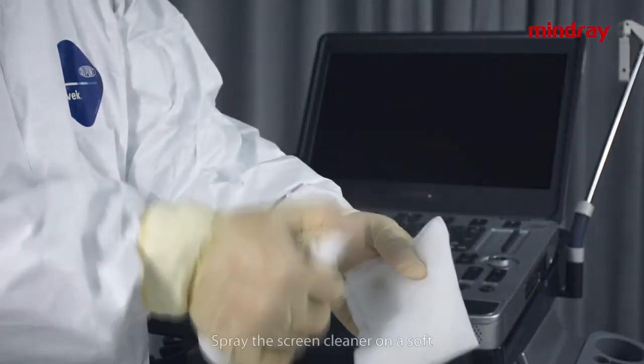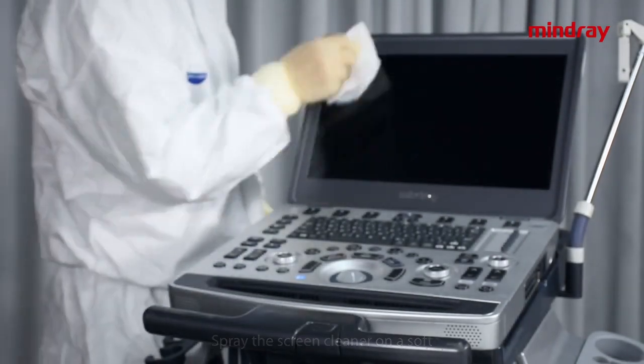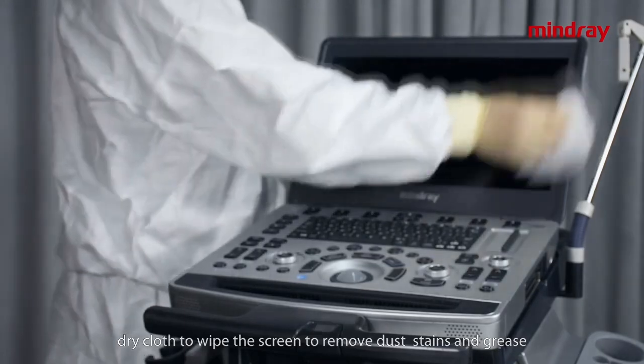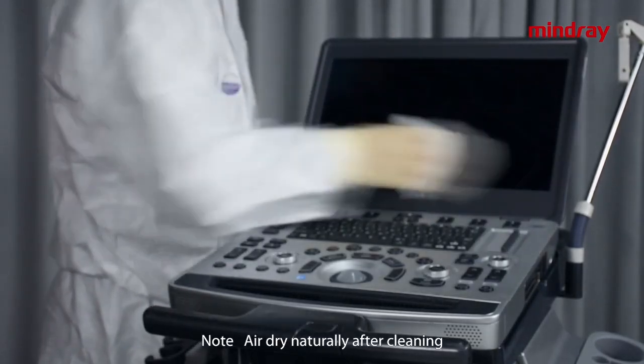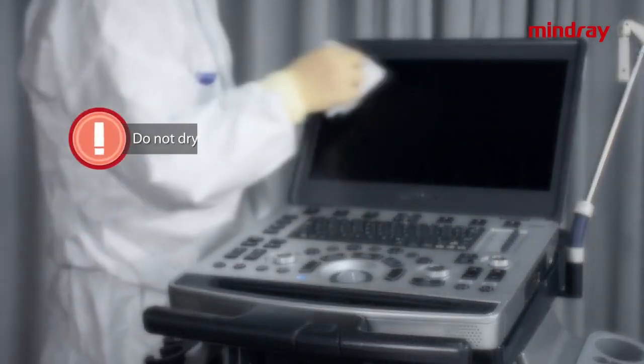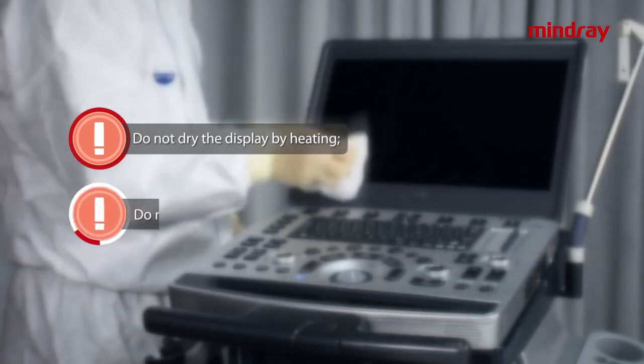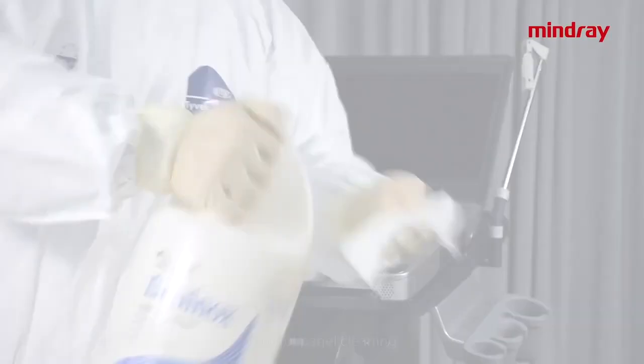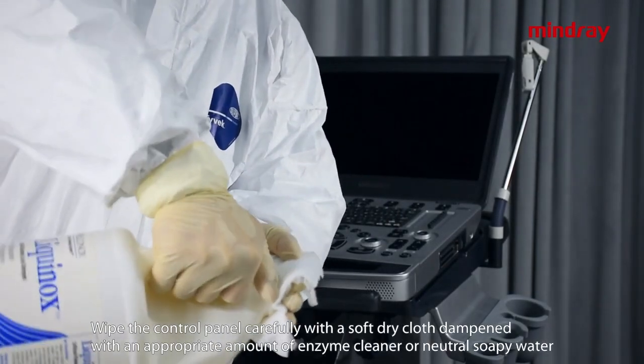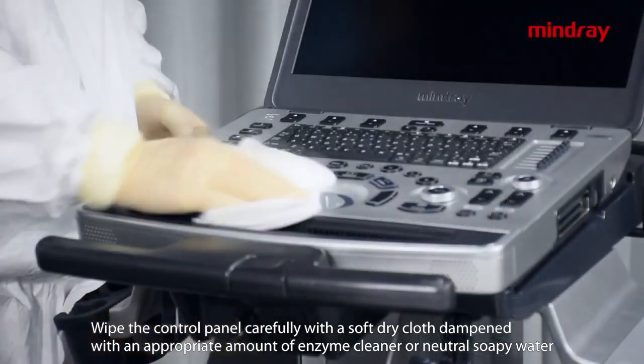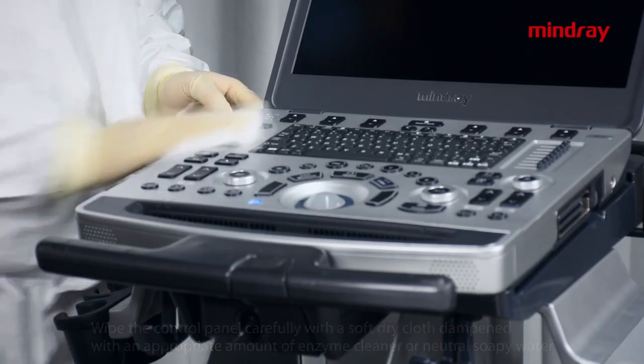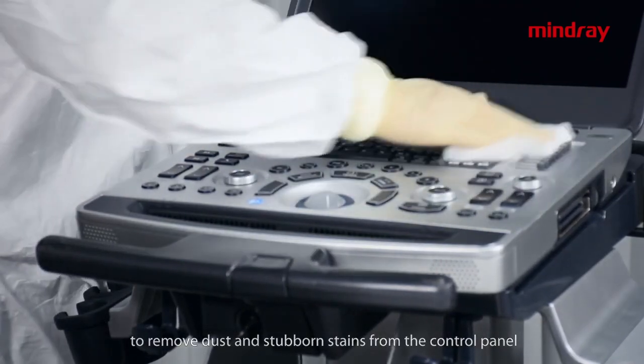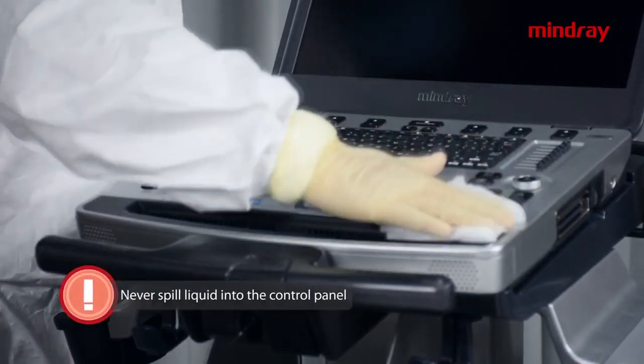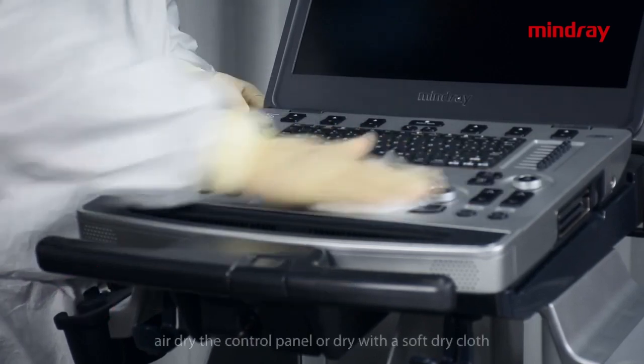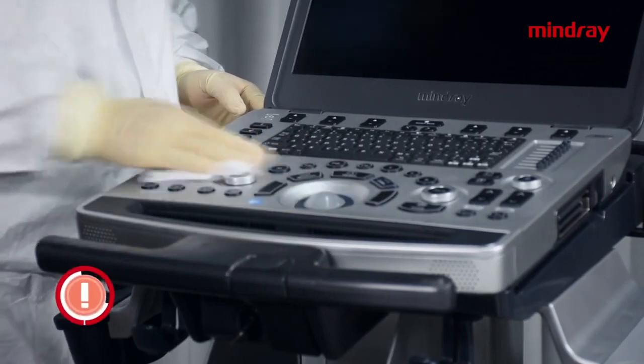Monitor cleaning. Spray the screen cleaner on a soft, dry cloth to wipe out the screen to remove dust, stain, and grease. Note: air dry naturally after cleaning. Do not dry the display by heating. Do not wipe the display with alcohol, as alcohol will emulsify the display. Control panel cleaning. Wipe the control panel carefully with a soft dry cloth dampened with an appropriate amount of enzyme cleaner or neutral soapy water to remove dust and stubborn stains from the control panel. Caution: never spill liquid into the control panel. After wiping, air dry the control panel or dry with a soft dry cloth. Never dry the control panel by heating.